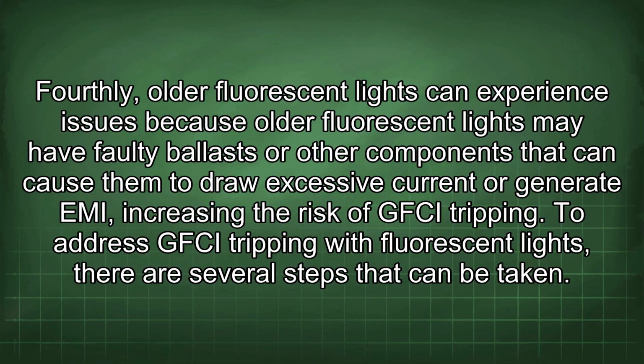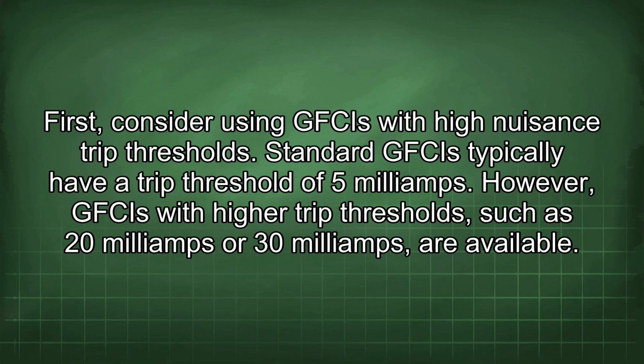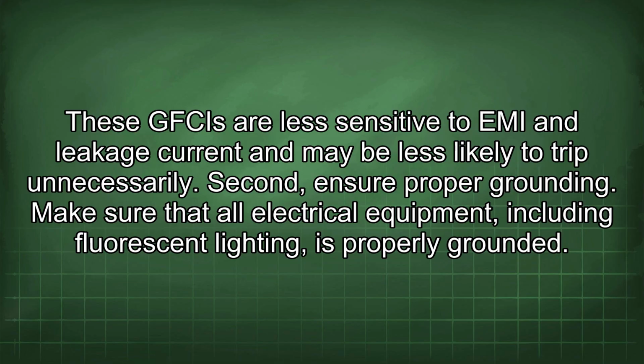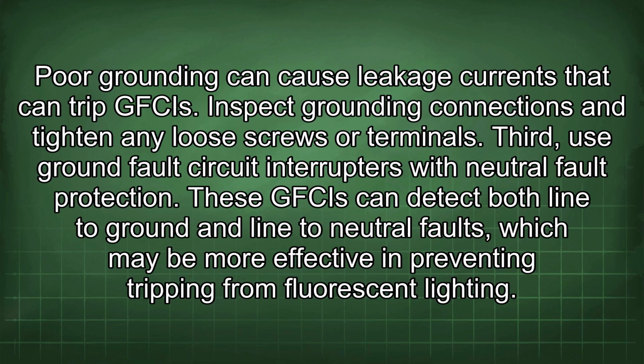To address GFCI tripping with fluorescent lights, there are several steps that can be taken. First, consider using GFCIs with high nuisance trip thresholds. Standard GFCIs typically have a trip threshold of 5 mA. However, GFCIs with high trip thresholds, such as 20 mA or 30 mA, are available. These GFCIs are less sensitive to EMI and leakage current and may be less likely to trip unnecessarily. Second, ensure proper grounding. Make sure that all electrical equipment, including fluorescent lighting, is properly grounded. Poor grounding can cause leakage currents that can trip GFCIs. Inspect grounding connections and tighten any loose screws or terminals.